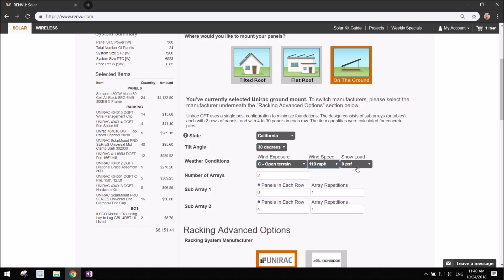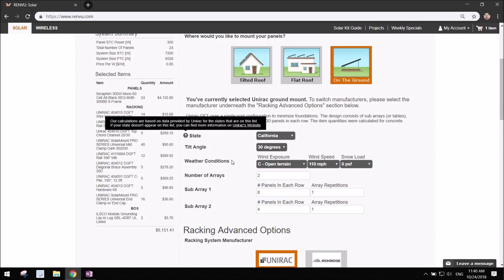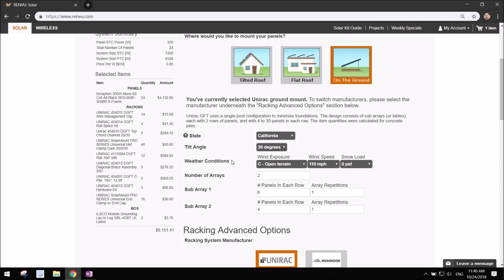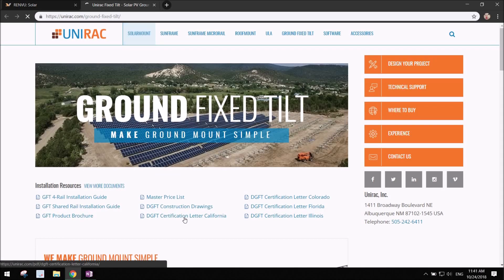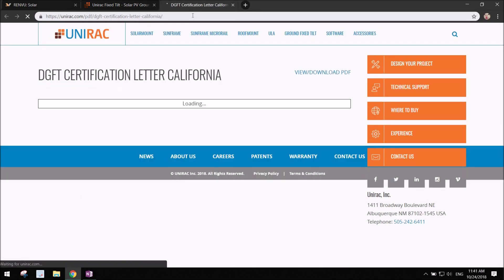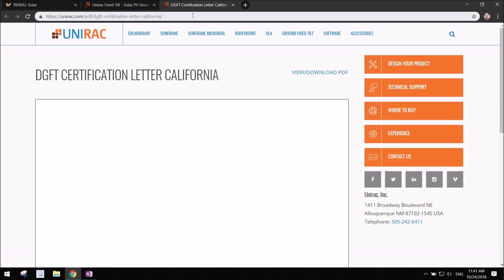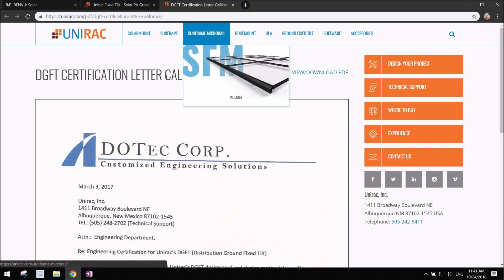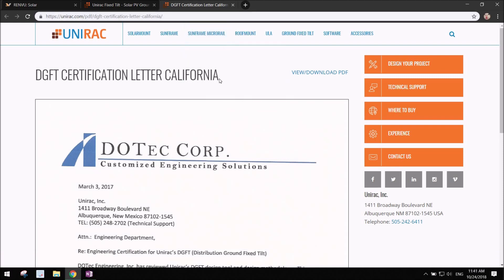The other thing is wind speed, you know what do we choose here, and snow load, it's like I don't really know what the snow load is for my area, that's a good question. So there's two things we can do here. One thing is you can check with your local AHJ to see what wind exposure, wind speed, and snow loads they require for your area or they suggest. You can check with ASHRAE, you could check with other structural engineers. But an easy way is to check with UNIRAC and find your certification letter. California has one, not all states have them, but you can guess and check based on your location.